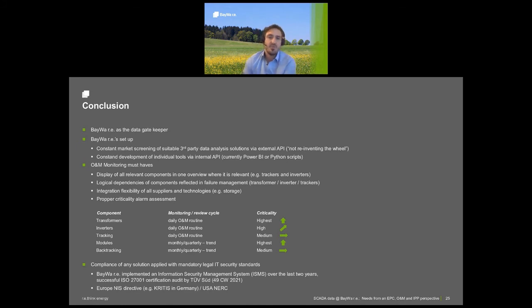A string inverter, of course, we want to see it as soon as possible, but the priority must be less. That's a daily O&M business. Tracking algorithms, very important as well. But if one tracker fails to find the optimized angle one day, I think it's acceptable. On a general view, the backtracking and the algorithms have to be in line, but there must be a proper hierarchy when it comes to alarming.